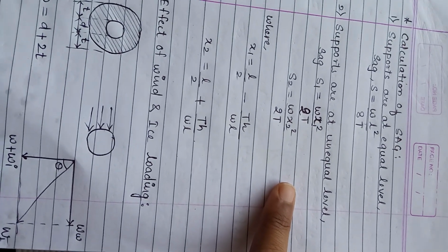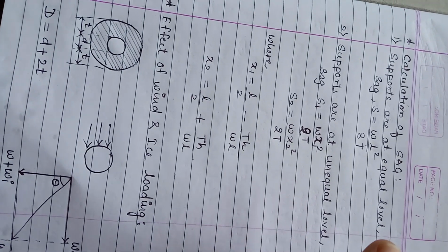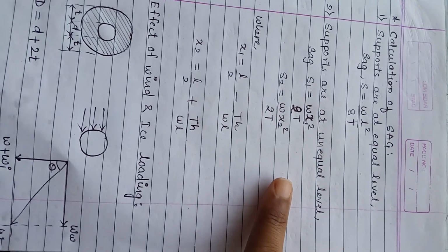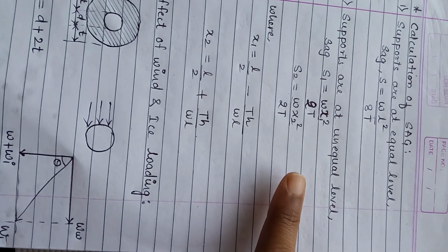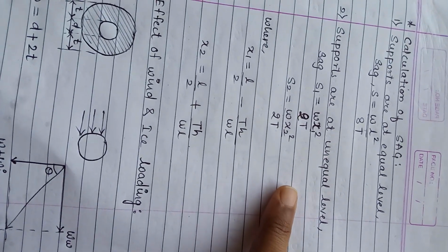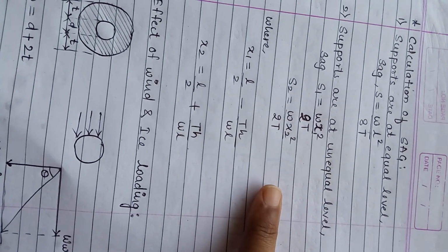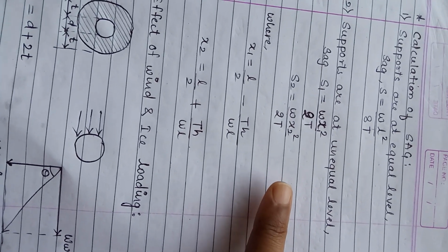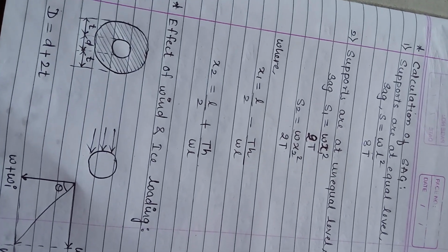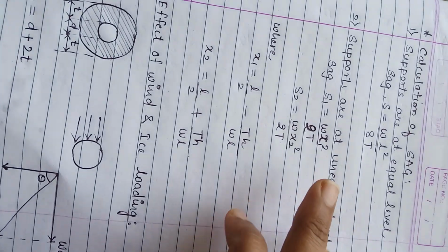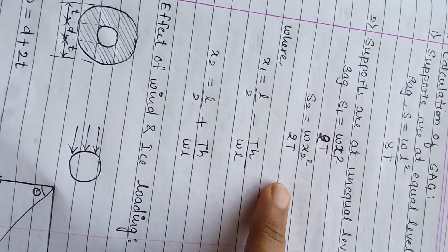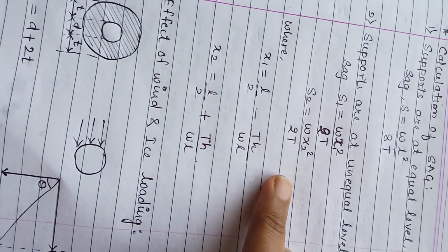If we talk about hilly regions, then if the transmission line is installed in hilly regions, the supports or the poles will be at unequal level. So in order to calculate the sag when the poles are at unequal level, the formula is S1 and S2, because there will be two sags, one from the pole at the upper level and one from the pole at the lower level, right?